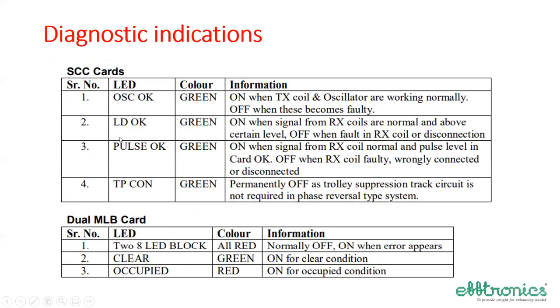Now, electronic equipment, as we have said, has to provide its health through data, but many times to access the data you require, again, a processor-based system. Instead of that, on the card itself they provide certain diagnostics, like the test point, pulse OK, which is a green LED. When it is on, there is a signal from RX. When the pulse level is on, the card is okay; when it is off, the RX coil is faulty, or it is wrongly connected or disconnected. So using these LEDs, it is possible to find out the problem with the cards and then replace them.